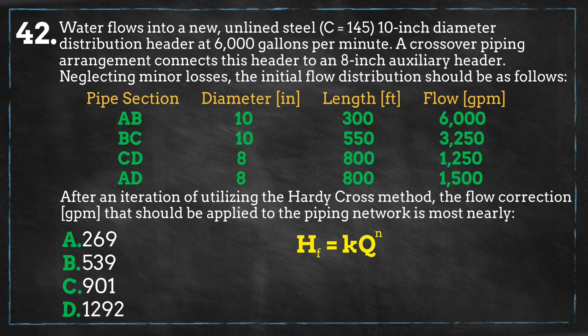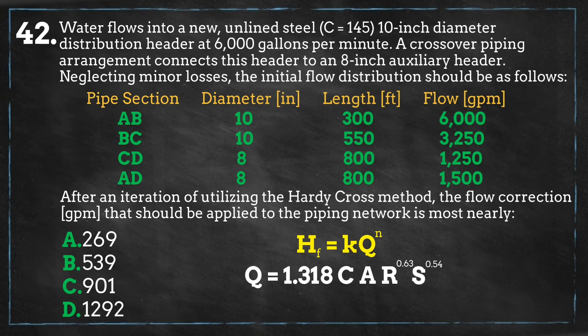Over the past few episodes, we have used multiple equations to correlate head loss, flow, and pipe dimensions. For this problem, let's use the Hazen-Williams equation from episode 38. The Hazen-Williams equation gives q as the flow rate in cubic feet per second, c as the Hazen-Williams roughness coefficient, a as the cross-sectional area of the pipe, and s as the slope of the pipe. Realizing that the hydraulic radius r for a circular pipe is one-fourth of the diameter, and that our flow rate is in gallons per minute, we can simplify the equation.